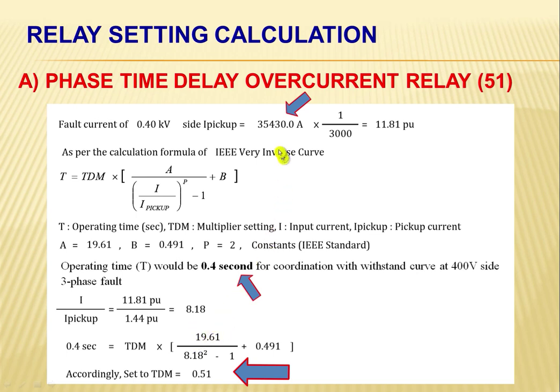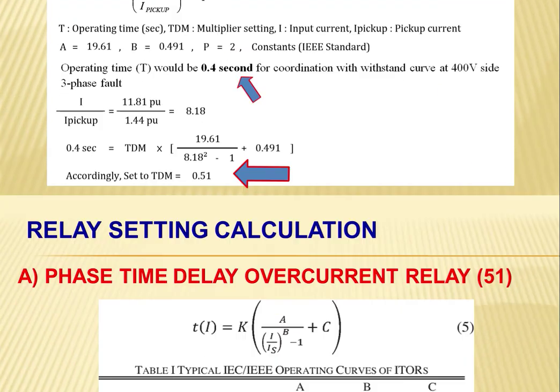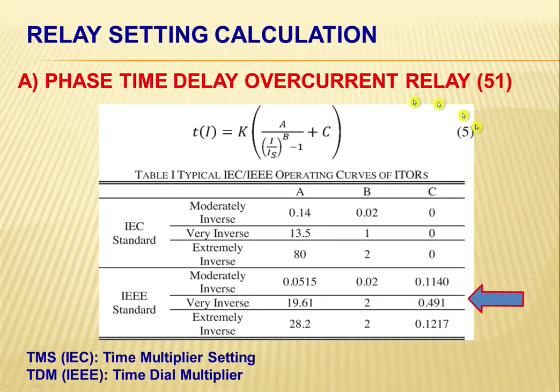based on these given values and based on our actual short circuit on the secondary side of the transformer. Okay? So, this is the formula that we have discussed earlier. The same formula also applies when we're going to use the IEC standard. Ours, we use the IEEE standard, very inverse curve. So we have here the constant values for A and for B and also for C. For the IEC standard, the value for C is equal to 0 only. Okay. Please take note that TMS and TDM are analogous terminology.